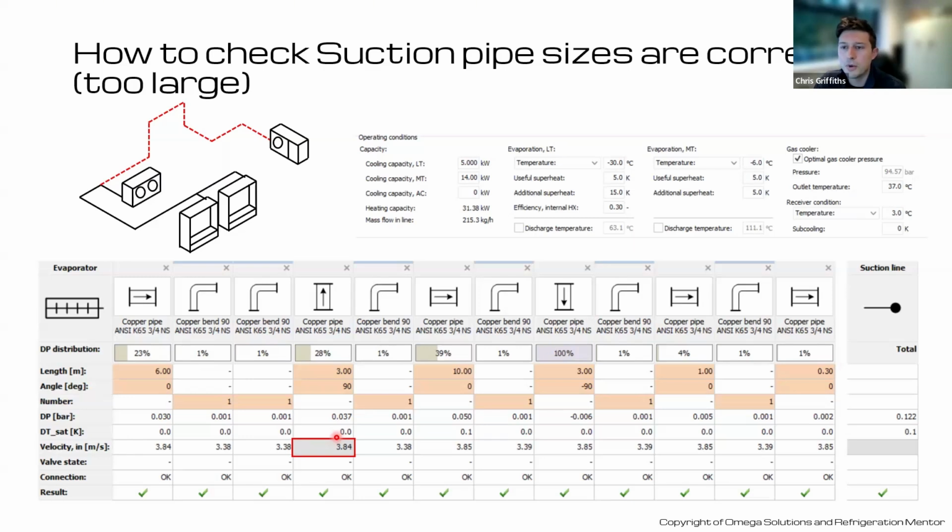But then sometimes you fall into the risk of people getting complacent and thinking, oh, because we didn't do it on that site and didn't do it on that site, well, we don't need to for this one, despite what the design drawings say. And then they'll put the same pipe size in and then wonder why at part load conditions, all those cabinets on that island start to fall over sideways. Yeah. Not naming any names, that's fine. There's always some fun arguments of that on site.